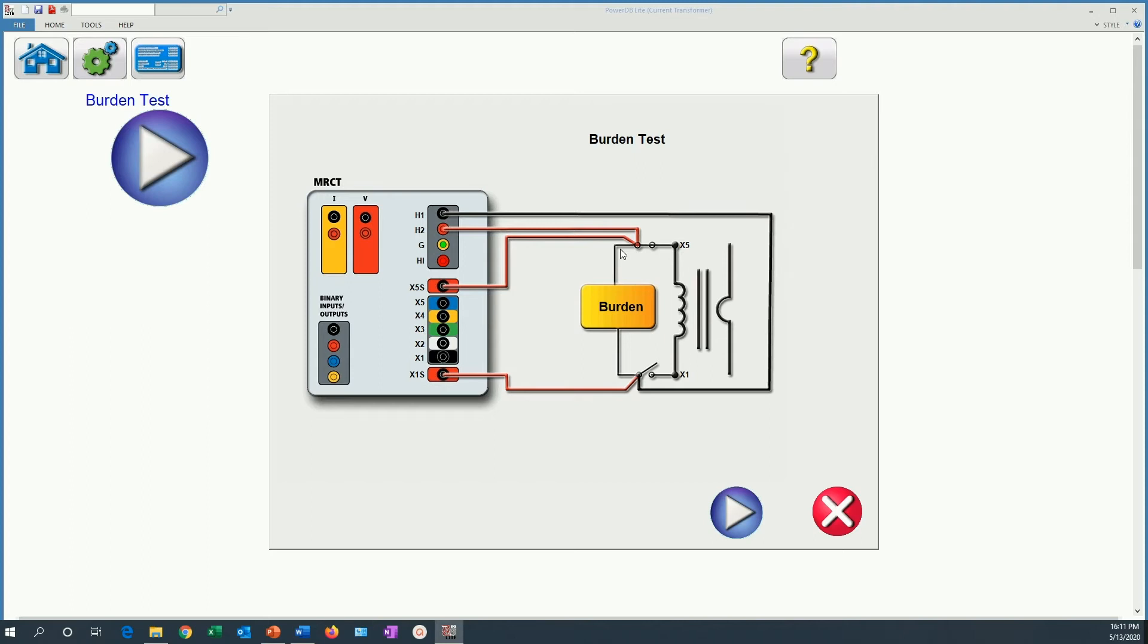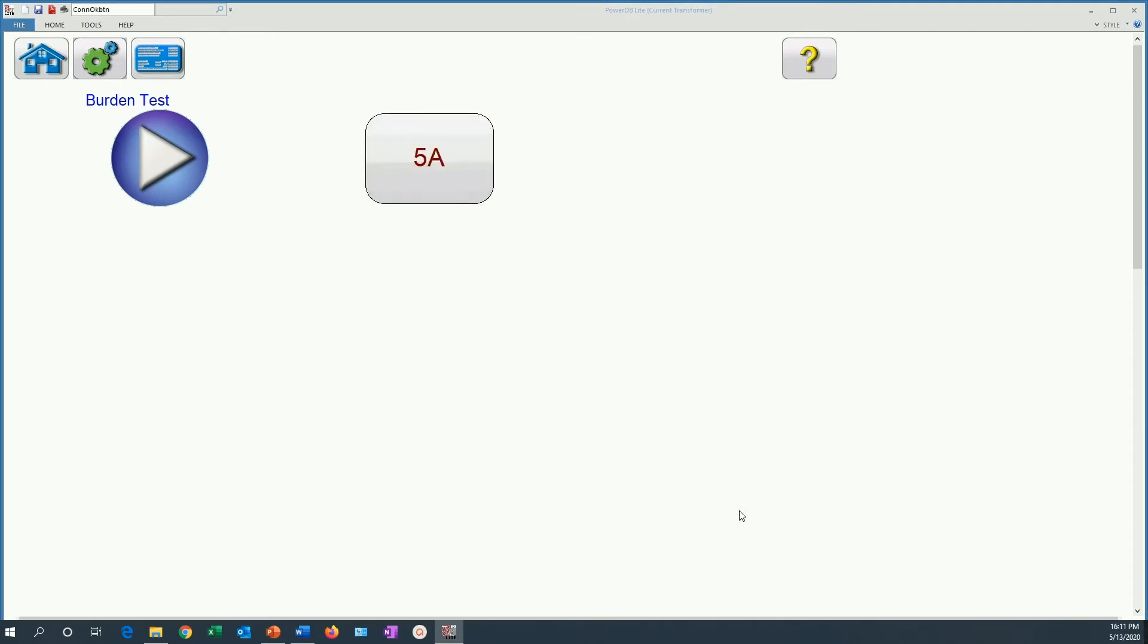The problem with that is that you could cause those relays to trip. So you have to be very careful when you are doing a burden test to make sure that you are not going to cause any unwanted tripping in the system. Take every precaution necessary for that. After we have checked that our connections are proper, we click here.